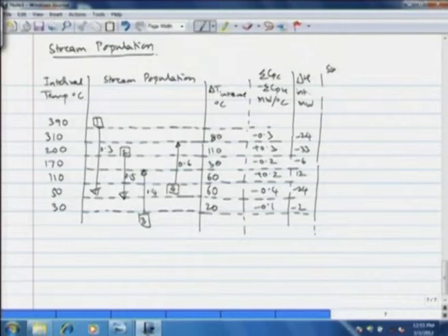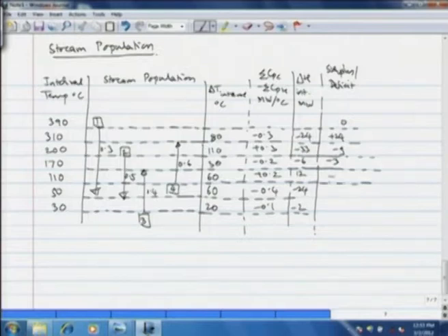and then surplus deficit of heat. So in the first interval we have plus 24, then minus 9, 33 taken off, then minus 3, minus 15, 9 and 11, and thus we see here is that the maximum deficit is in the fifth interval of minus 15 megawatt.